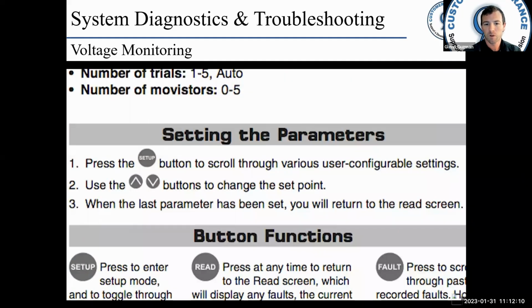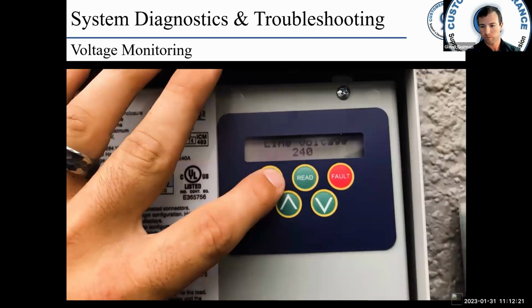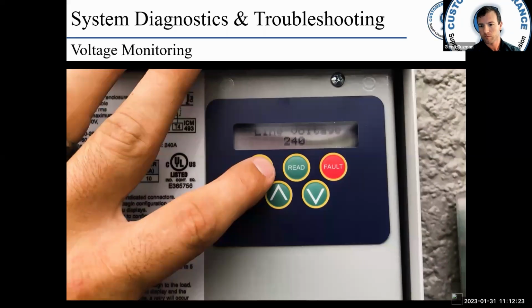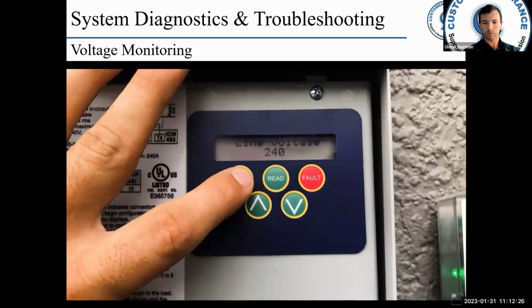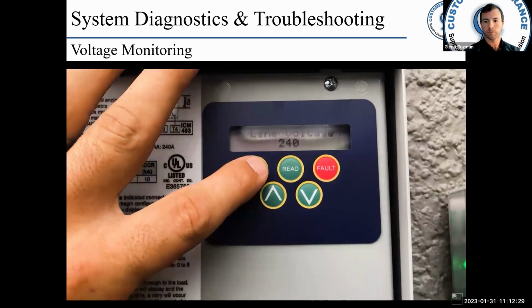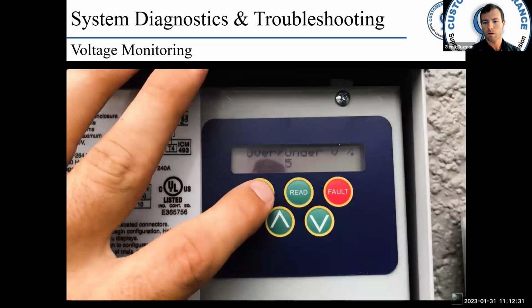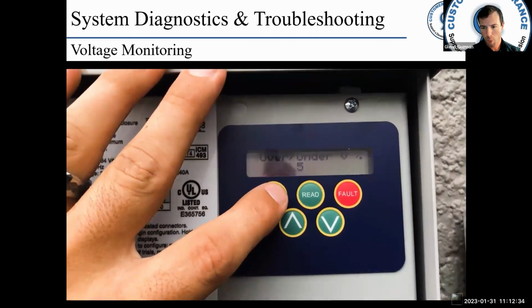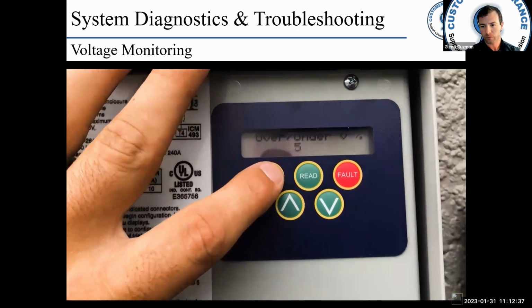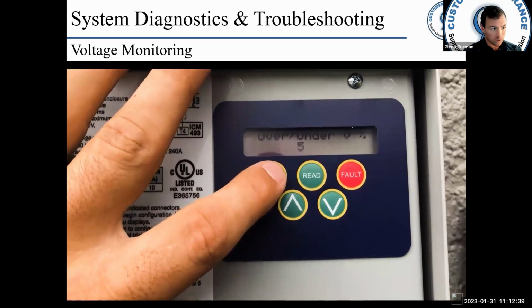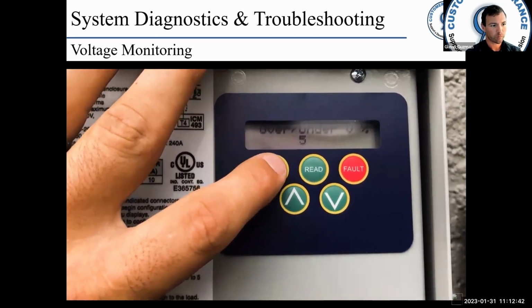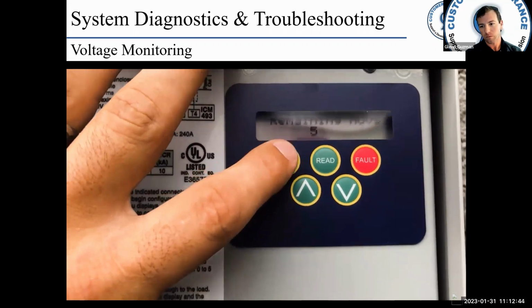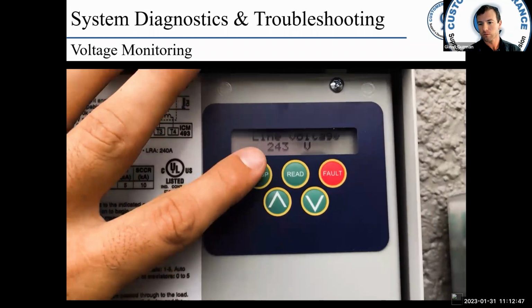Okay, so for our setup on the ICM 493, you just push the actual setup button. So first you're going to push the setup. It's going to ask you the line voltage. So what is this appliance? Is it a 120, 240, whatever it may be? This particular one's a 240. Over under voltage percentage. So we are going with 5%. Under or over 240 volts will actually open the contacts that are providing voltage to our load. So we want to go with 5%.